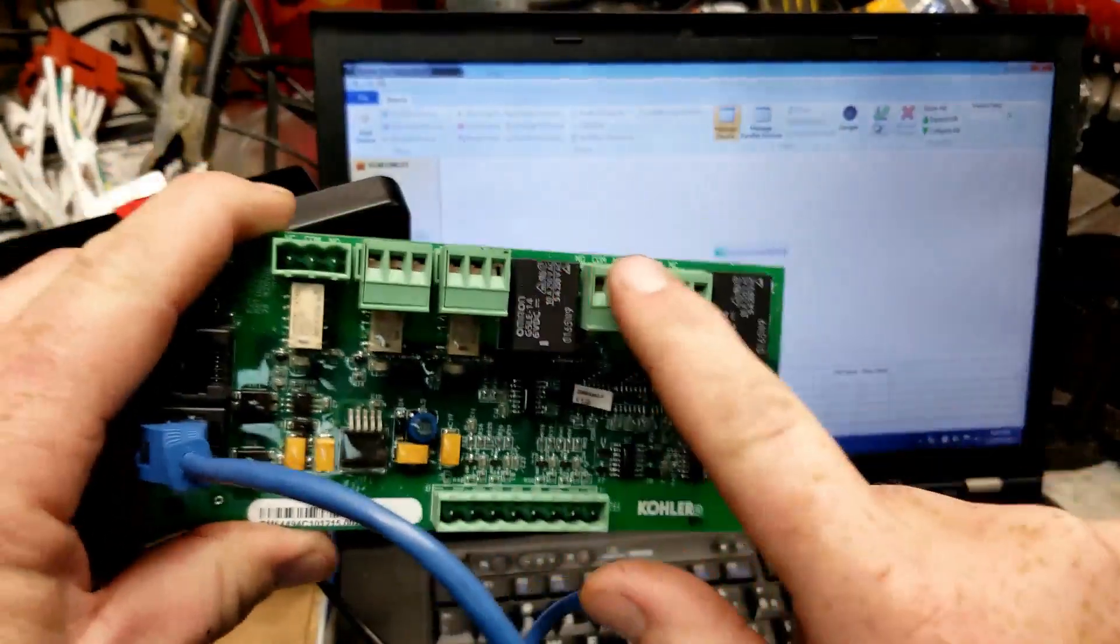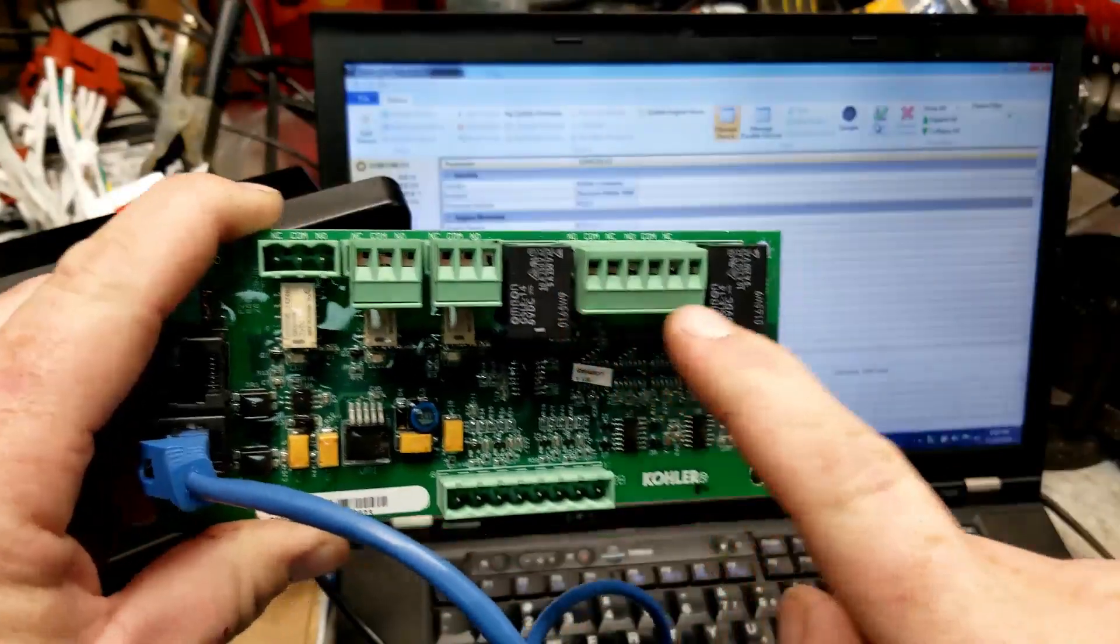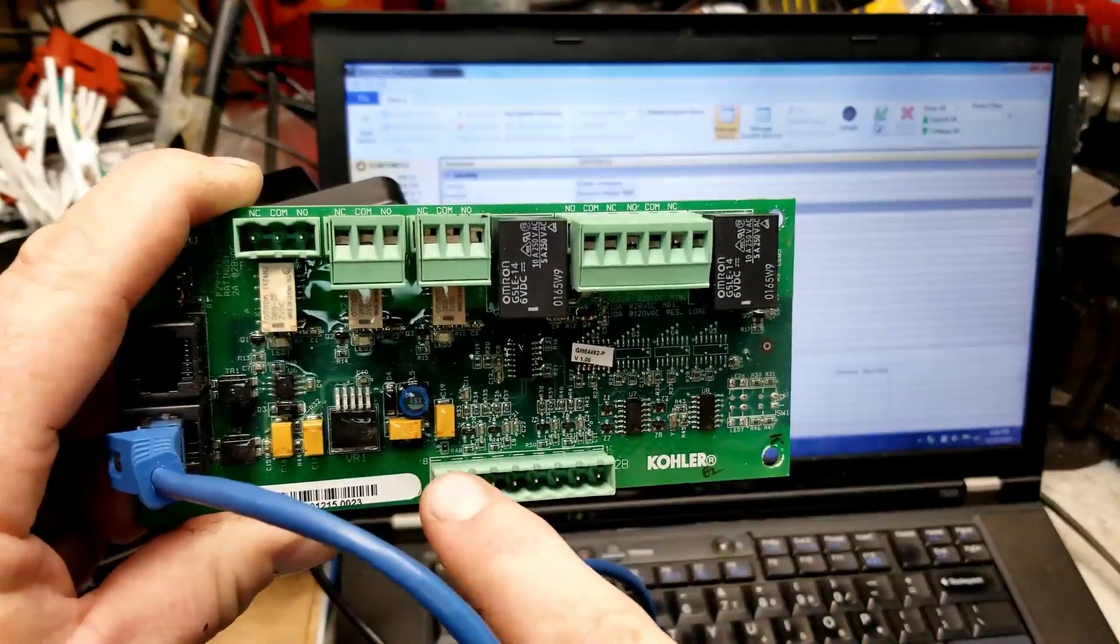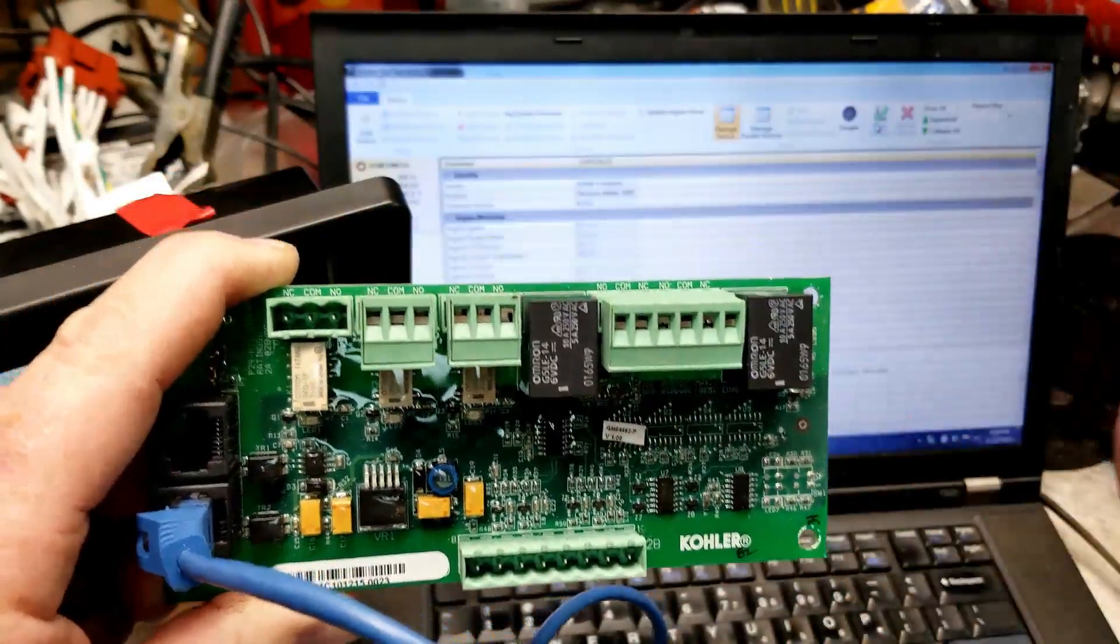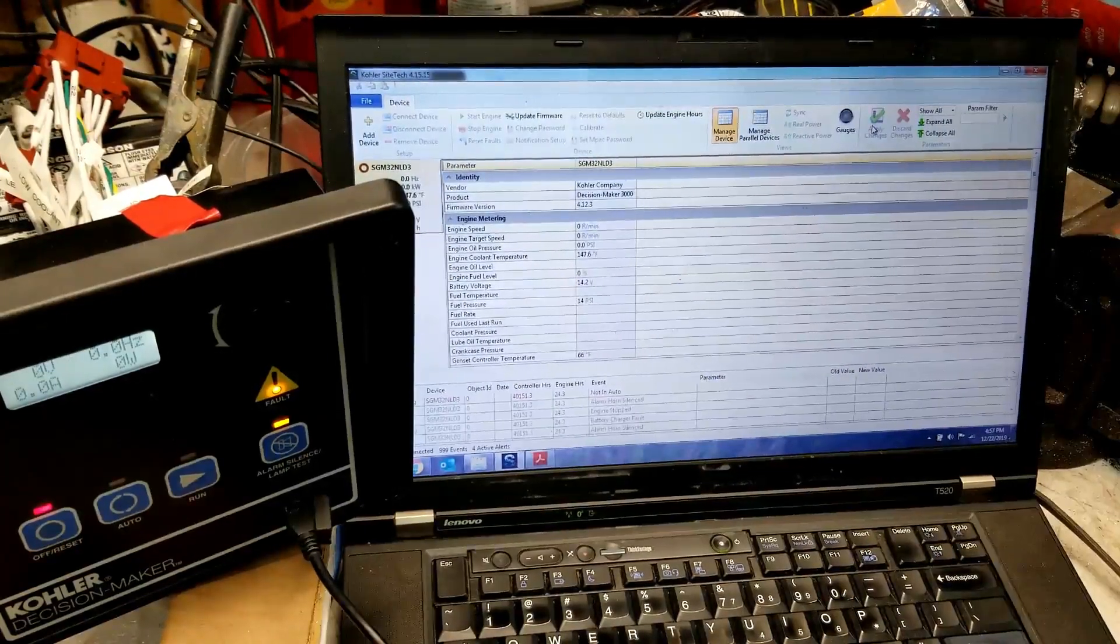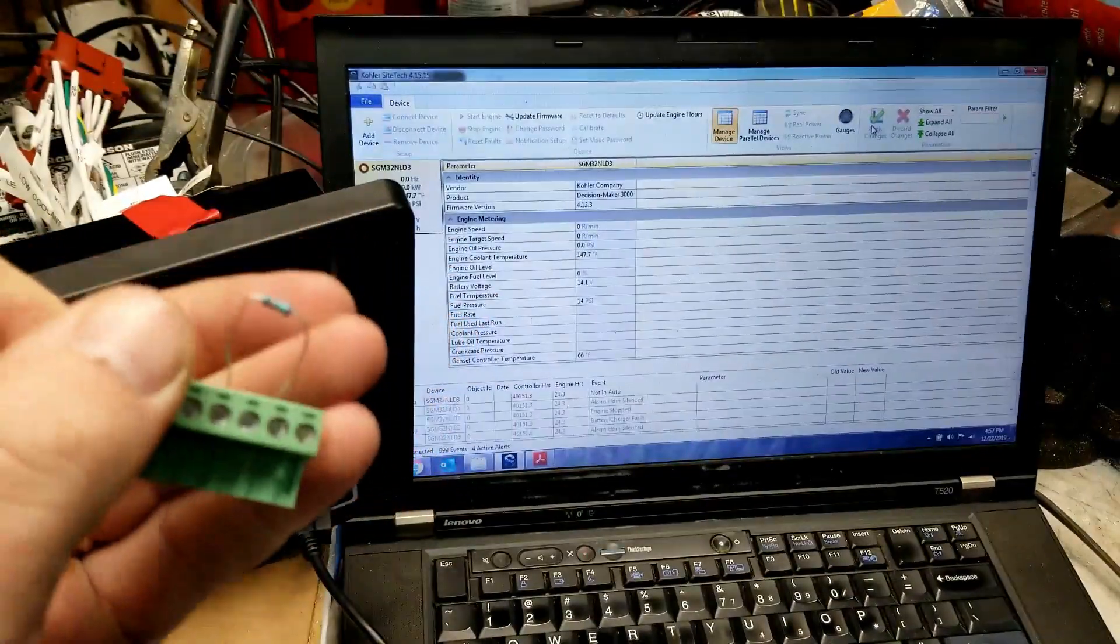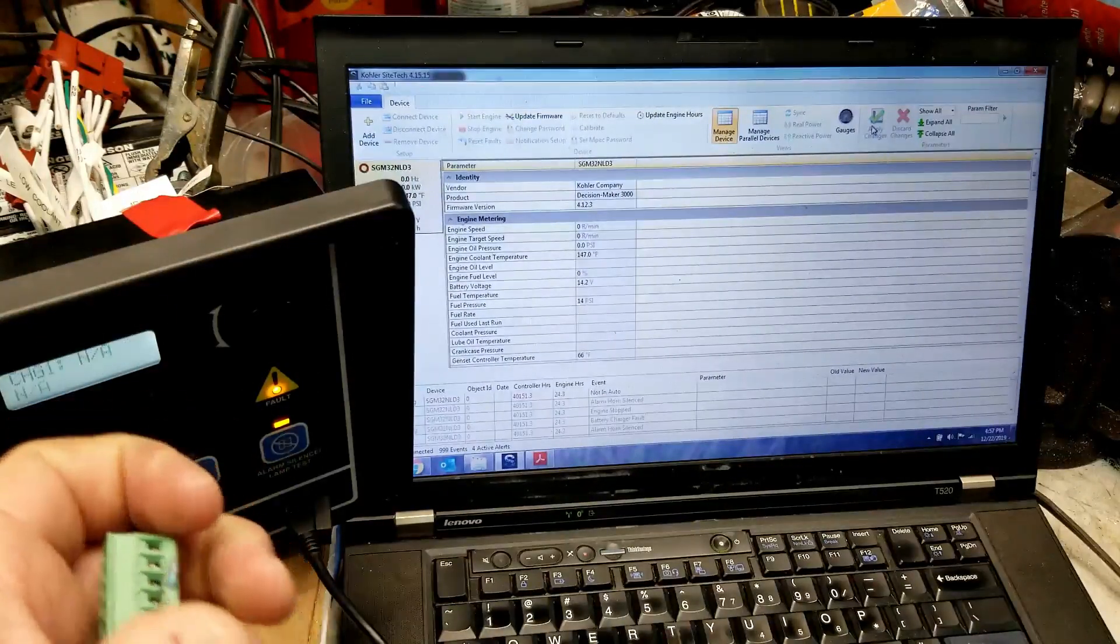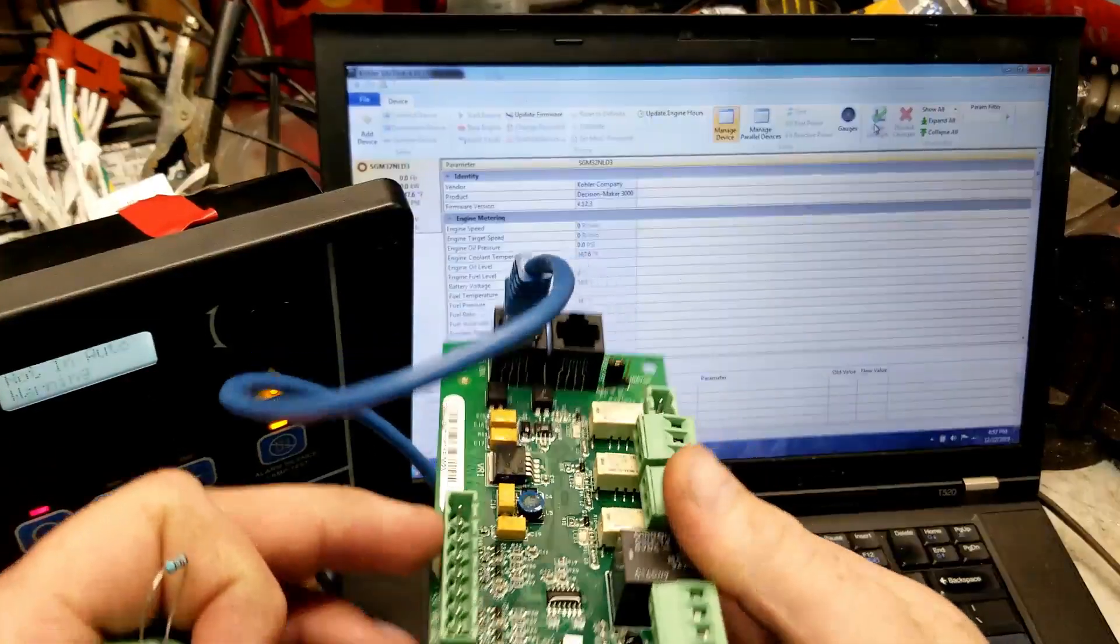Everyone uses these five relay outputs. And you have two analog inputs right here. Then if you look in the book, it says this can be used as a digital input, but it didn't say how to do it. And I had to learn the hard way how to do it. And it involves taking a 120 ohm resistor, which is actually the same value as for the Modbus circuits, for an end-line resistor.